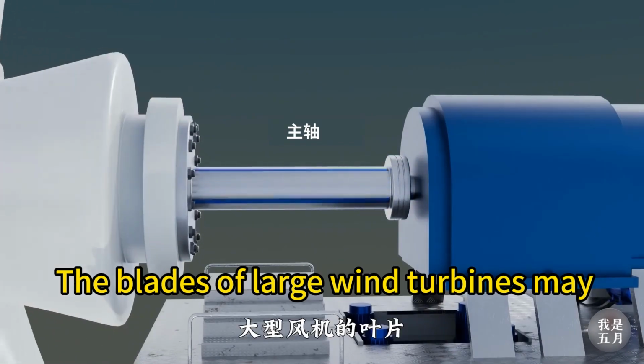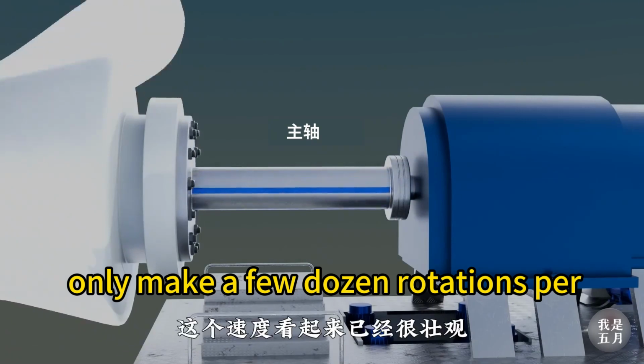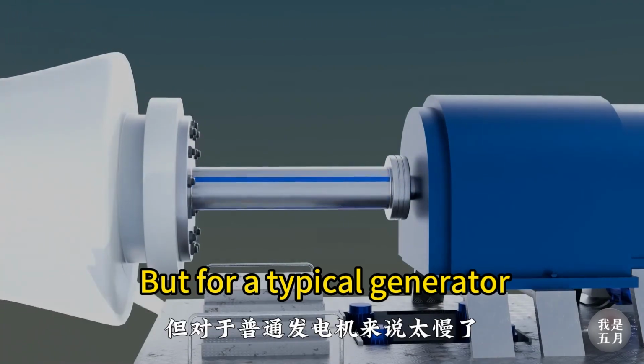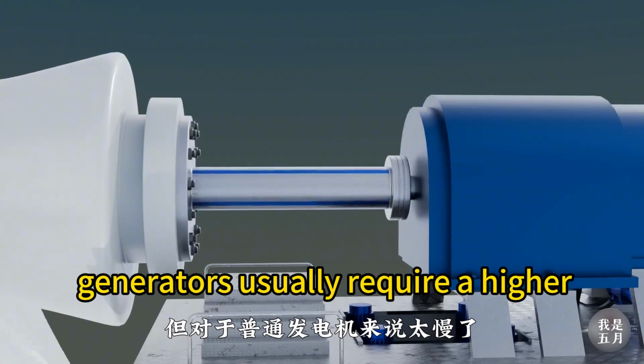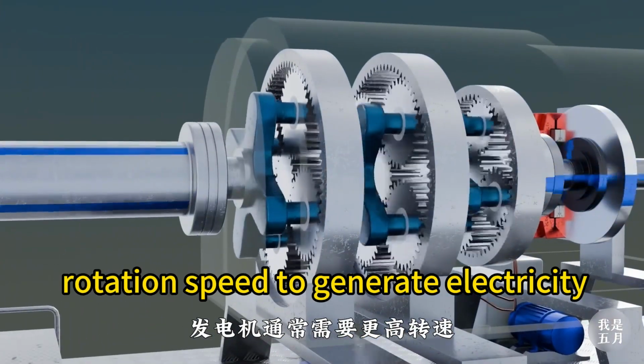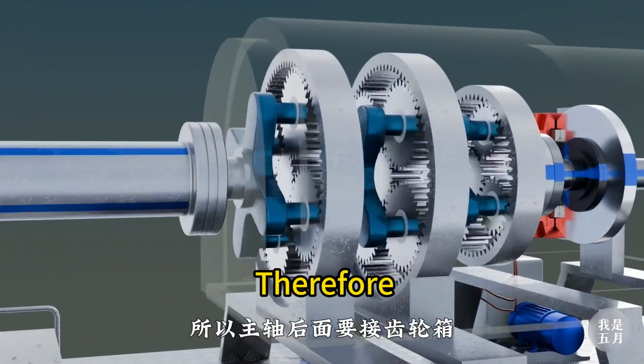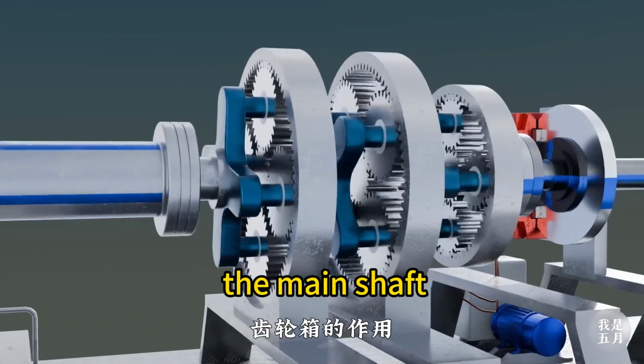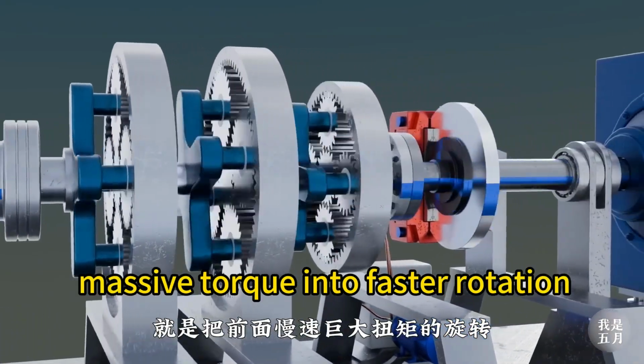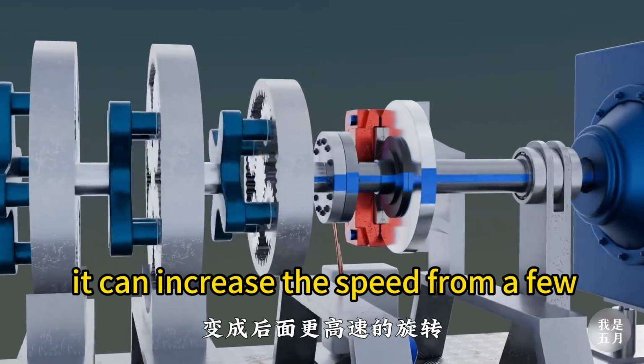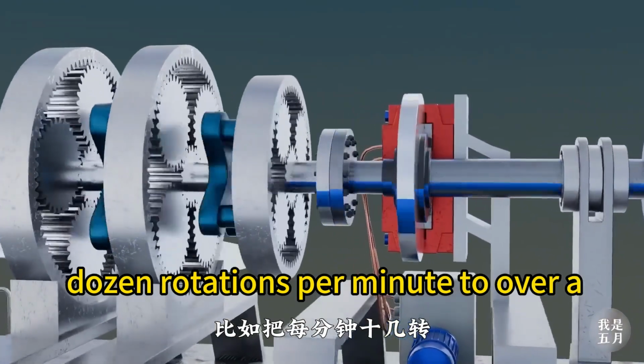The blades of large wind turbines may only make a few dozen rotations per minute, which already looks impressive. But for a typical generator, this speed is too slow. Generators usually require a higher rotation speed to generate electricity effectively. Therefore, a gearbox needs to be connected behind the main shaft, which converts the slow, massive torque into faster rotation. For example, it can increase the speed from a few dozen rotations per minute to over 1,000.